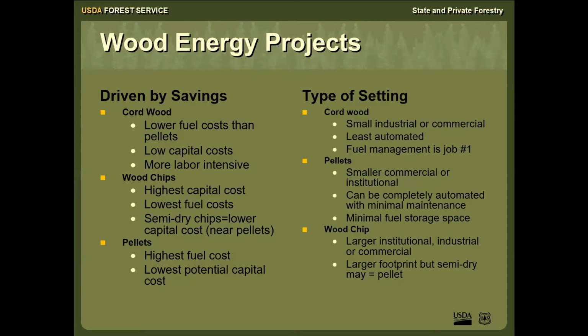Wood chip projects, we find, are higher capital cost, probably, and in most cases those are larger systems. The fuel costs are probably the lowest. With the new semi-dry chips, there's a reduced capital cost to some extent, because a number of larger pellet boilers are able to use semi-dry chips when their moisture content is below about 40%. That means the delivery, storage, and handling systems, as well as the boiler systems, are a bit less costly than the green chip version.